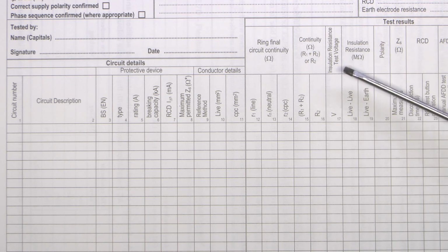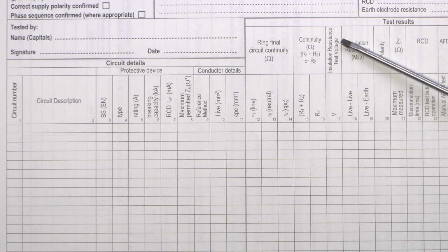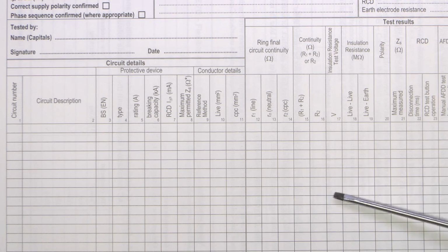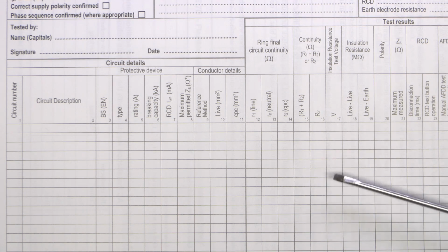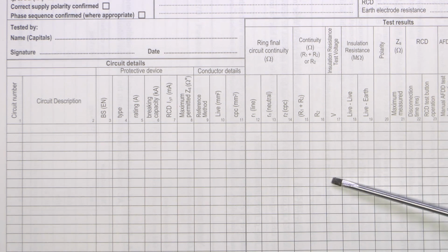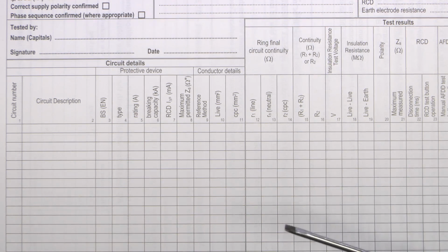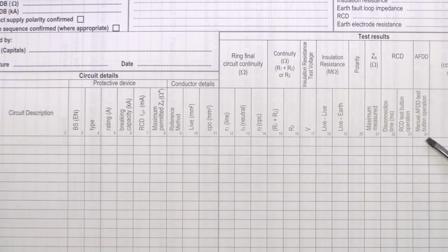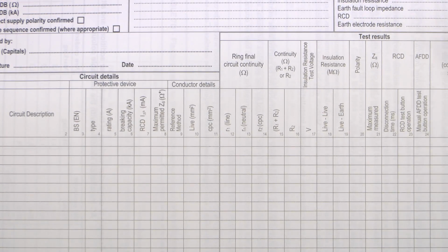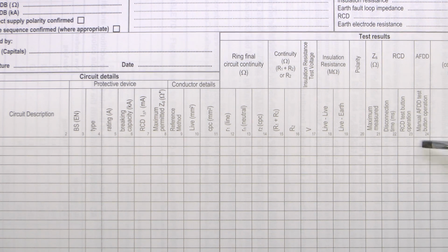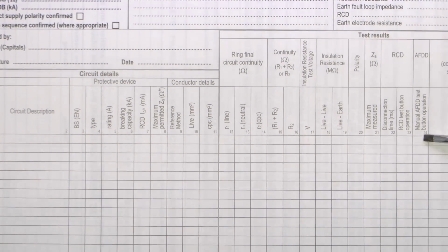Further on here we've got a new column for the insulation resistance test voltage, so again you're filling that in there. 500 volts for most single phase installations, although again other voltages are available. And then the final column here is the one for AFDDs, or arc fault detection devices. Basically it's just confirming that you've operated it with the test button, and it did operate satisfactorily. So yeah, nothing too surprising with that.